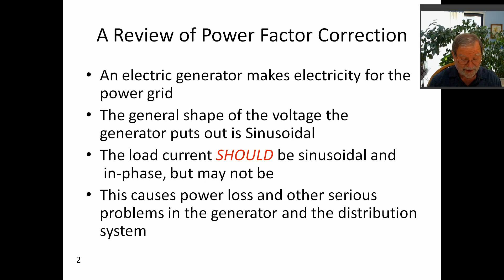If a current wave is non-sinusoidal, the higher harmonics cause power loss in the system and inefficiency because the system is designed for 60 hertz operation. In addition, the generator may find itself alternately slowing and accelerating in strange ways over a cycle. Either condition is unacceptable. Power factor correction is the process of changing poorly conditioned loads into loads that look resistive, where the current follows the voltage in a sinusoidal waveform.